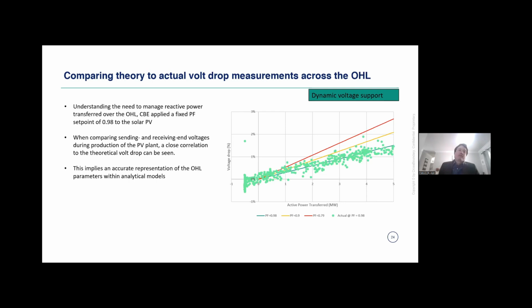So if we now compare what the theory told us versus the actual volt drop measurements across the overhead line, we can see that we are pretty much spot on in terms of our representation of the overhead line parameters within our analytical models. You'll see there's a slight negative measurement in some cases. This would be during the night when the power flows in the reverse direction across the line. So what this entailed was we were able to defer the upgrade of the line by reducing the amount of reactive power that's being transferred across the line, and rather keeping the solar PV at a fixed power factor.